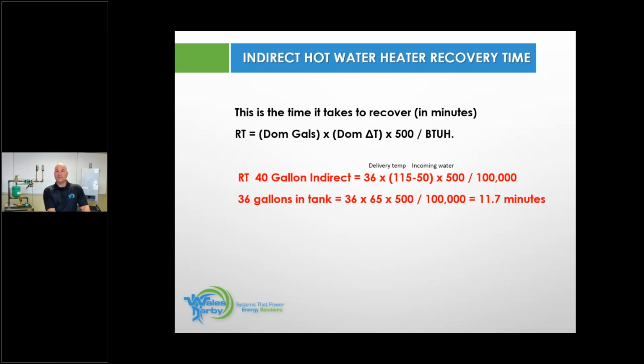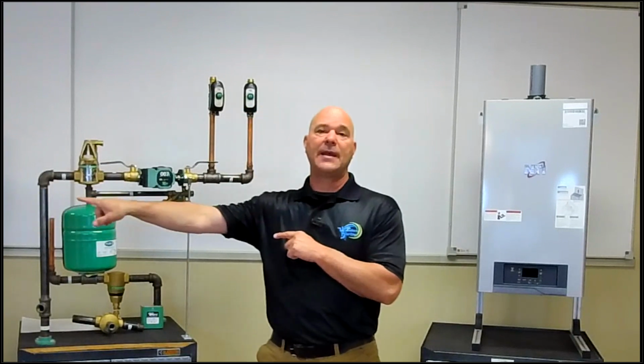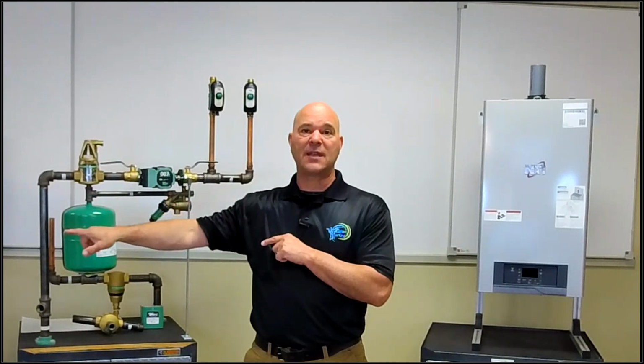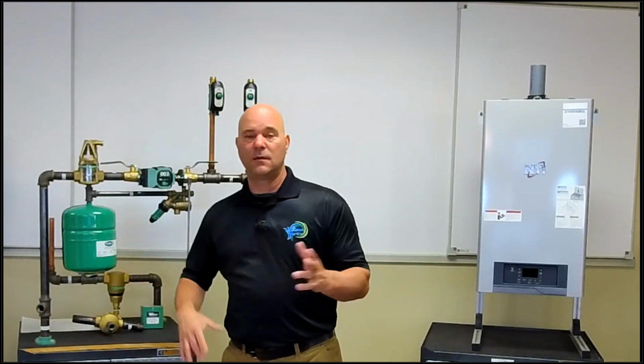Everybody with me on that? That means my boiler is 100,000, my piping has the ability to carry 100,000 BTU, and I have the proper circulator size to drive that indirect to the capacity that it's capable of. What is that number? Well, a good 40-gallon indirect can absorb probably around 150,000 BTU. You get a 119-gallon indirect, a good one out there, you'll probably absorb about 350,000 BTU.